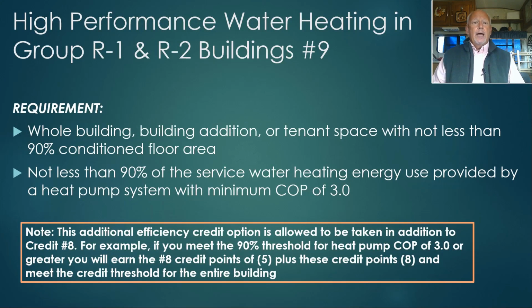For credit number 9, high-performance water heating in group R1 and R2 buildings, again, the water heating system has to supply the whole building, the addition, or tenant space with not less than 90% of the conditioned floor area. And then to meet that credit, not less than 90% of the service water heating energy use has to be provided by a heat pump system with a minimum COP of 3.0.